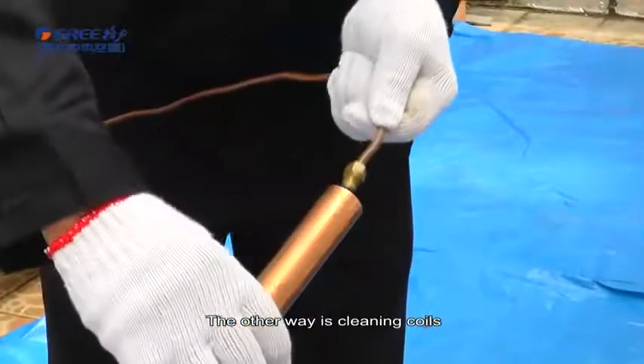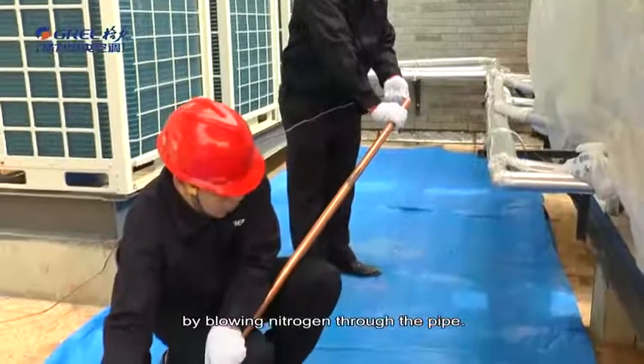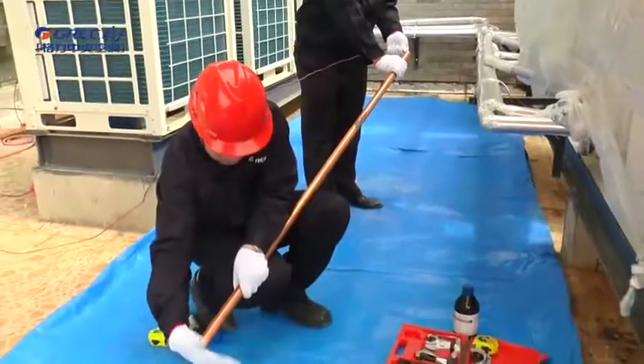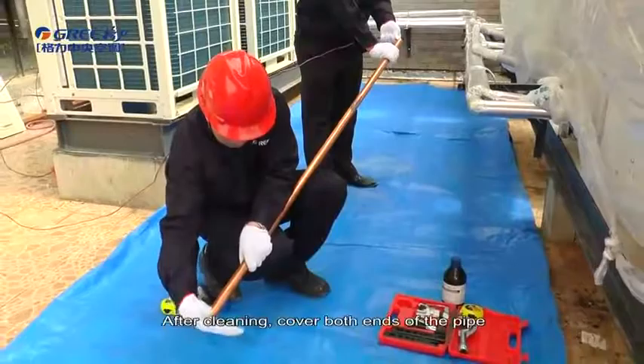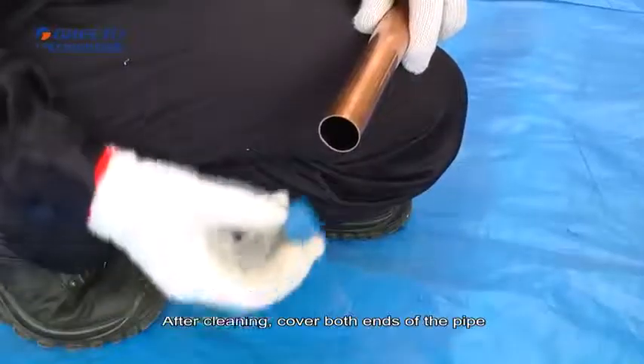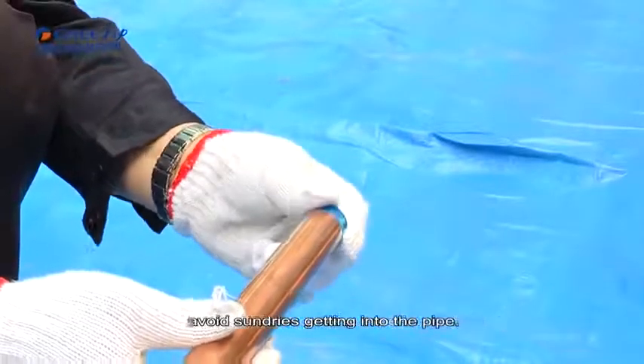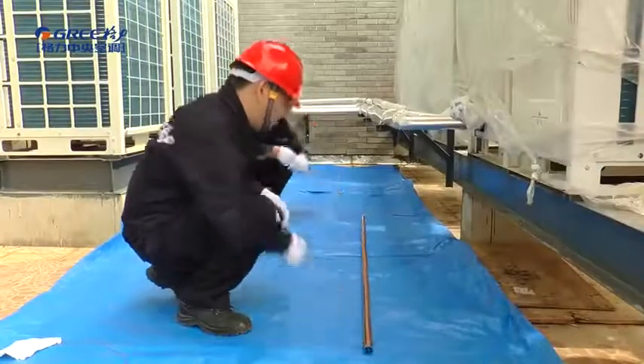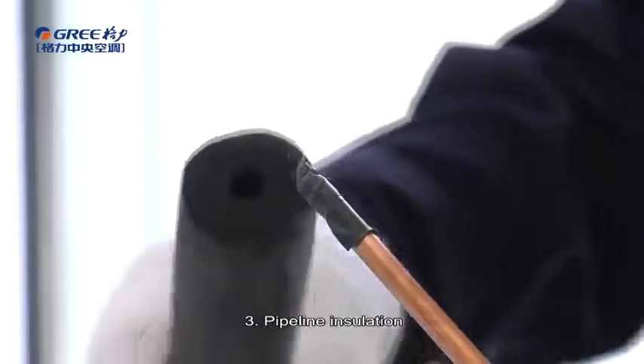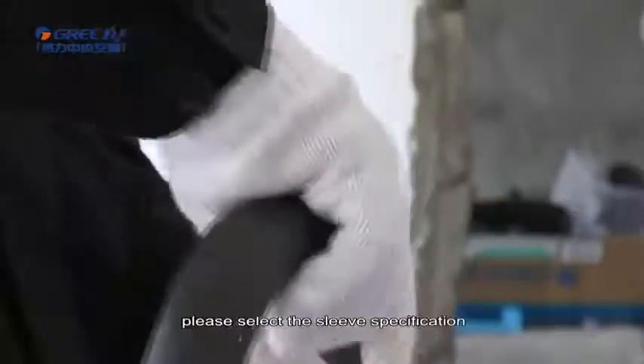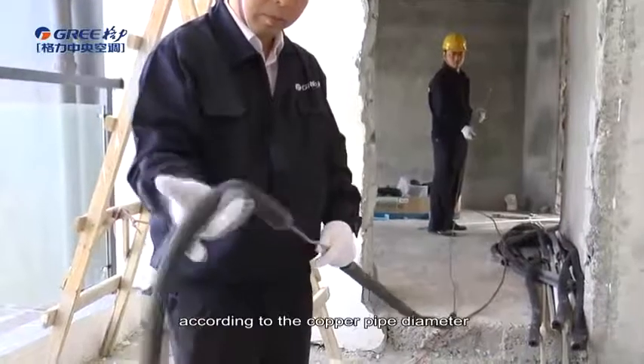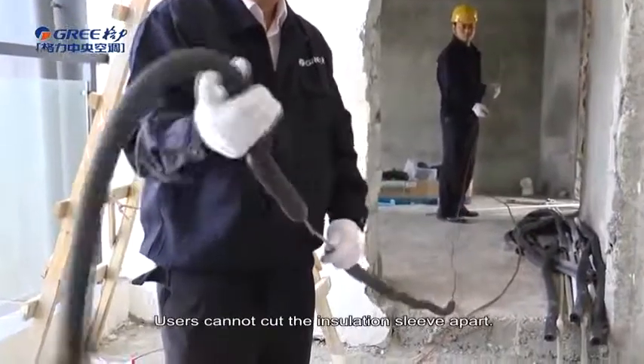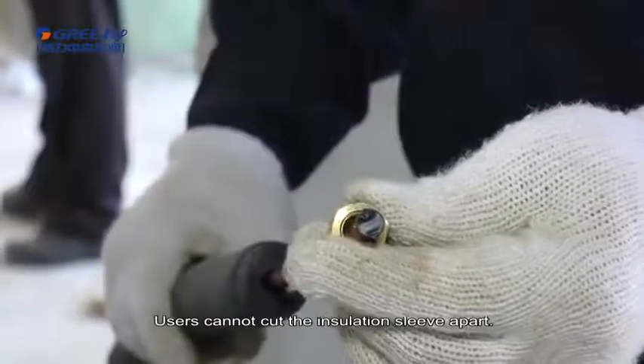The other way is cleaning coils by blowing nitrogen through the pipe. After cleaning, cover both ends of the pipe with sealing caps or adhesive tape immediately to avoid sundries getting into the pipe. Third, pipeline insulation. When adding the insulation sleeve, please select the sleeve specification according to the copper pipe diameter. Users cannot cut the insulation sleeve apart.